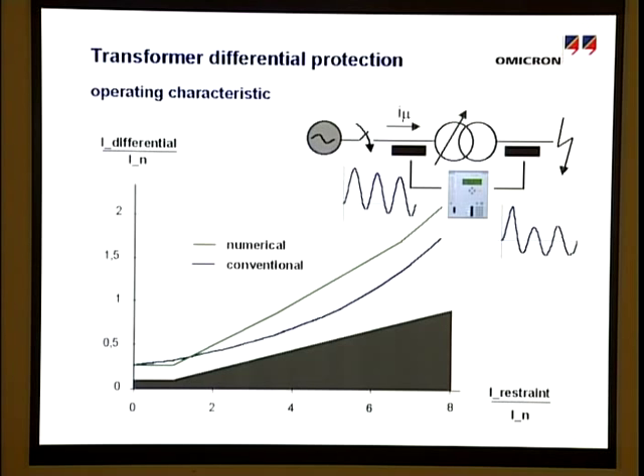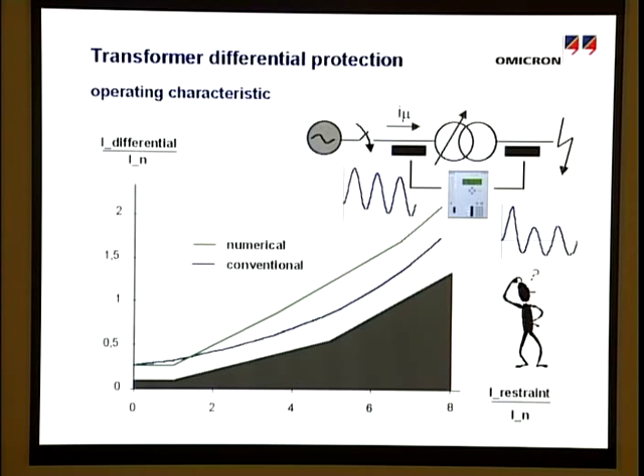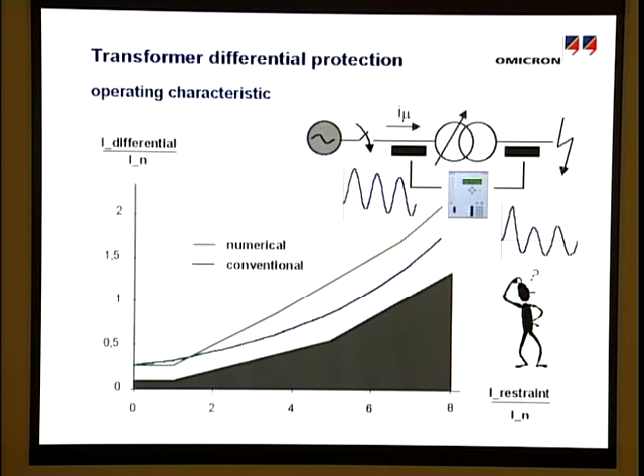While the effect of the first two differential currents can be calculated easily, the setting in the area of high stabilizing currents is difficult due to the non-sinusoidal behavior. Therefore, it is mainly based on experience. Many numerical relays are nowadays supplied with additional saturation detectors.